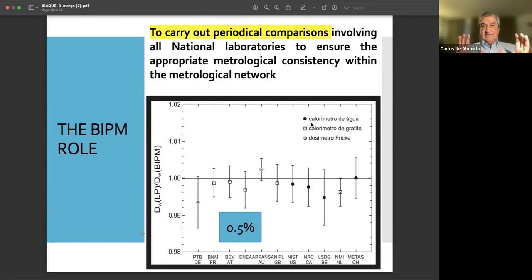So it was important for you to realize that when you measure a particular quantity at the hospital, this quantity is related to the calibration lab that has provided you with the calibration coefficient. And that lab, if it's not a primary standard, if it's a secondary standard, is connected to the primary standard. And the primary standards are all connected to the BIPM. Next slide.